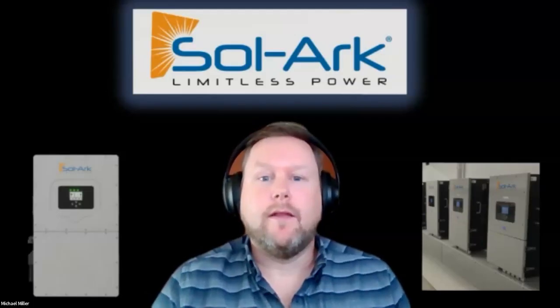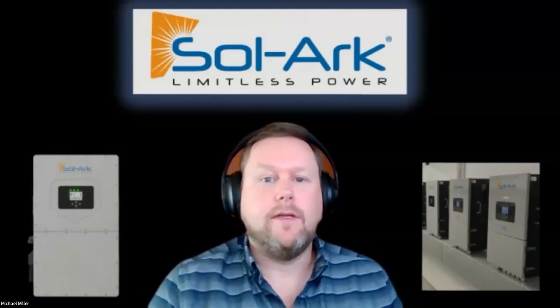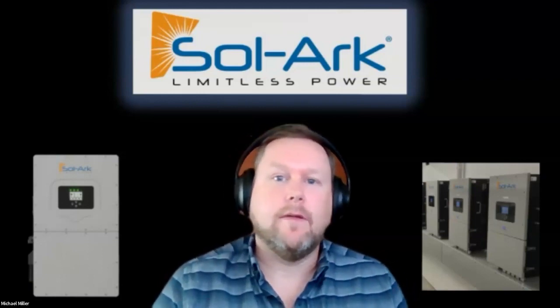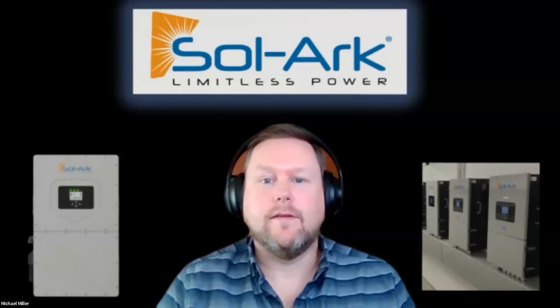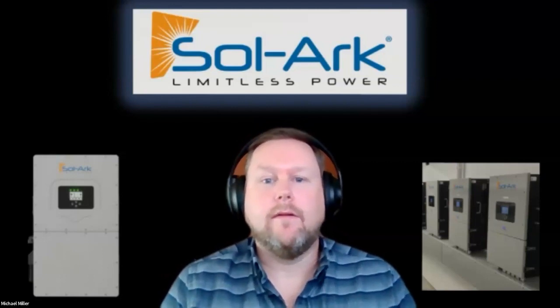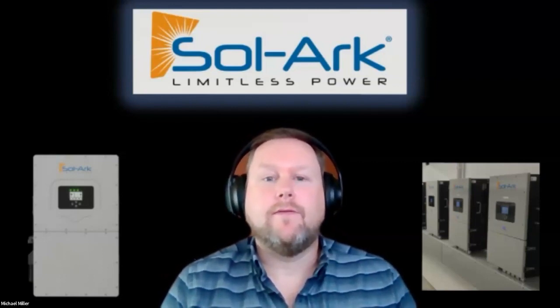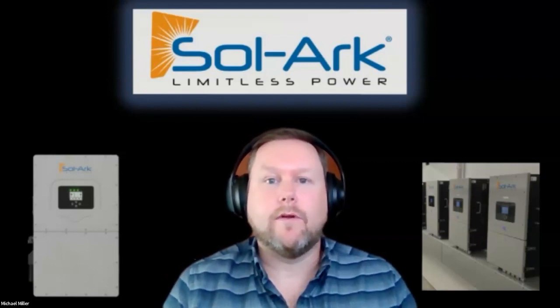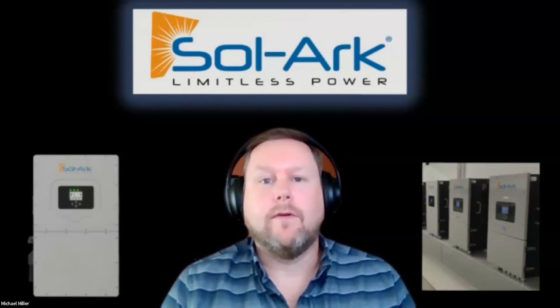Eric says: my understanding is that the 15K Sol-Ark inverter has one AC coupled input. How can the inverter connect to both an AC coupled PV array and a bidirectional EV charger? If you were to AC couple on the load side, you could do the EV charger on the GenPort input. That's a possibility. Vehicle to grid isn't quite ready and available yet, so stay tuned for more information. On the load side it's typically frequency shifting that's used, whereas with GenPort we have more control over the whole circuit. That's why we prefer the GenPort.